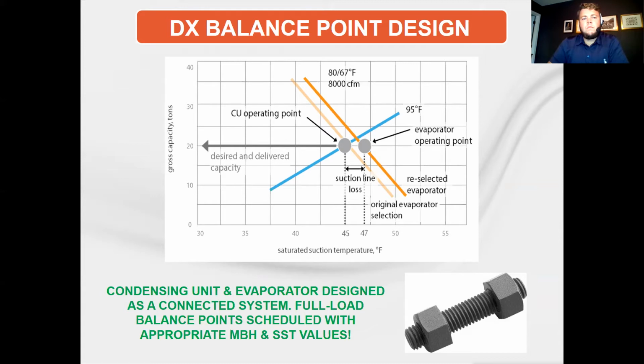So what this chart is showing you is that the balance point is really two different points on the curve, that the evaporator is 2 degrees warmer than the condensing unit. To schedule this equipment properly, the condensing unit schedule should show 20 tons at 45 degrees suction, and the air handler should show 20 tons at 47 degrees suction. If you do this, then it doesn't matter whose condensing unit or whose evaporator you're getting, as long as they meet those capacity constraints, the two should work together.